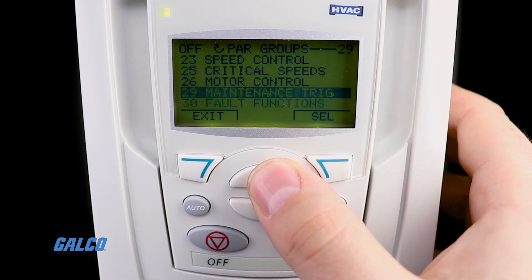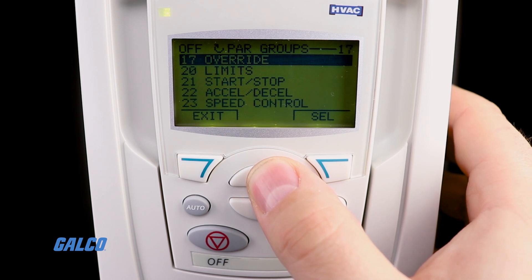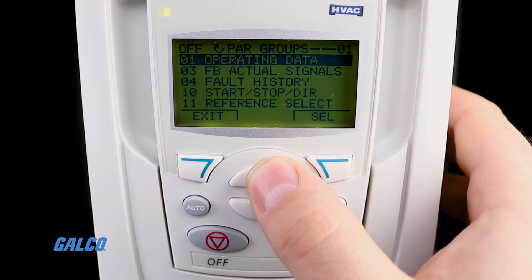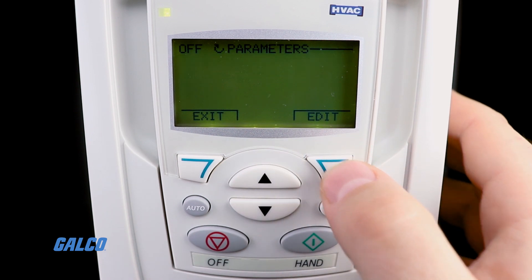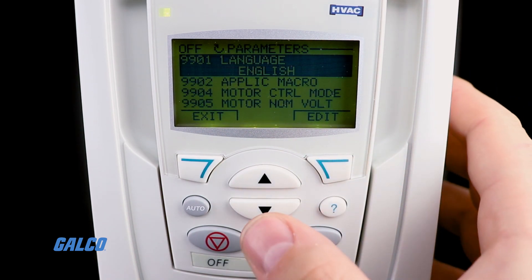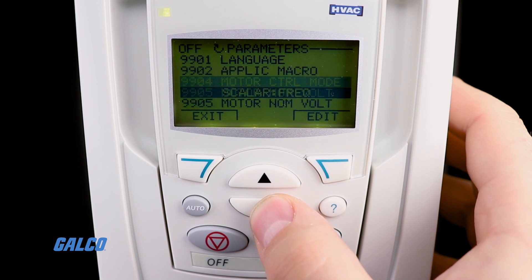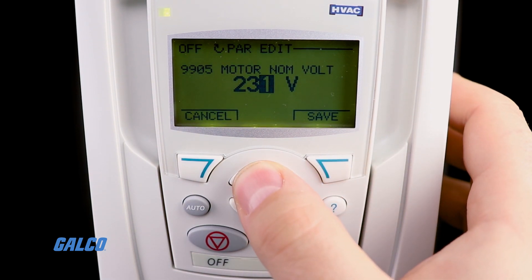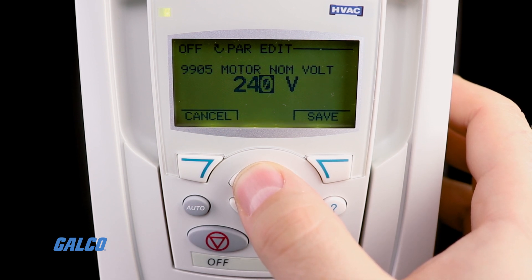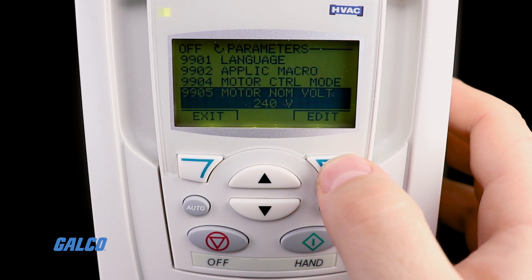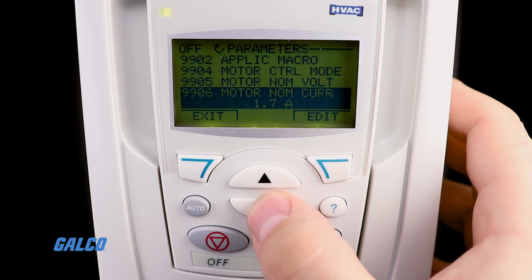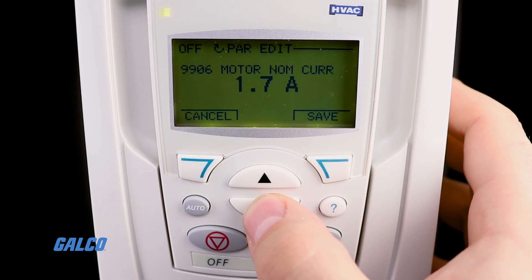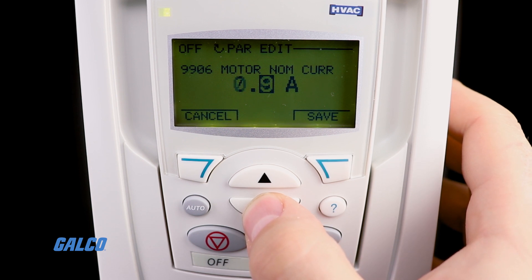Scroll to the parameter group that you would like to edit using the arrow keys and press the select button to open it. Now press the edit button to change the selected parameter value and adjust it as necessary. Note that the current set parameter value will appear below the highlighted parameter, and you can view the default parameter value at any time as a reference point by pressing the up and down buttons simultaneously.